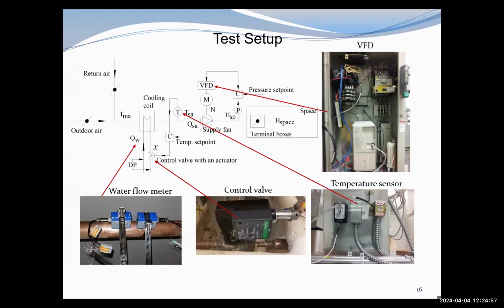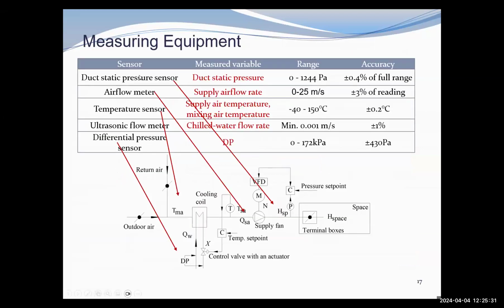To do the test, we have some test setup with sensors. The fan speed we can get from the VFD, and the supply air temperature is obtained from the temperature sensor here on the supply air duct. The valve position can be obtained from the control valve, and the water flow rate can be measured using the water flow meter, which is an ultrasonic flow meter here. Additionally, we also have other sensors installed in the system, such as a duct static pressure sensor to measure the duct static pressure, and the airflow meter to measure the supply air flow rate, and the temperature sensor to measure the mixing air temperature, and also the differential pressure sensor to measure the DP here.